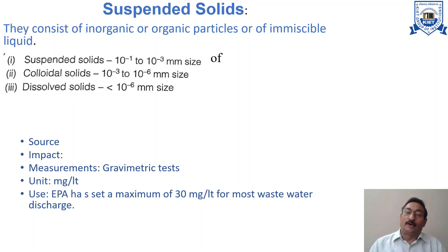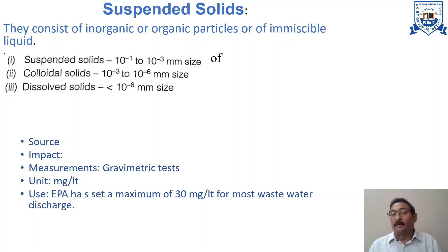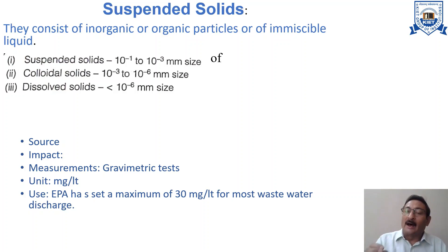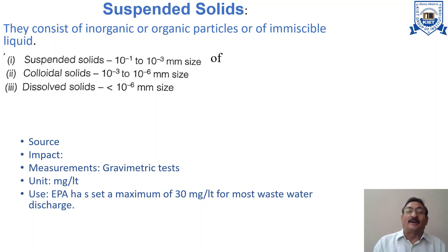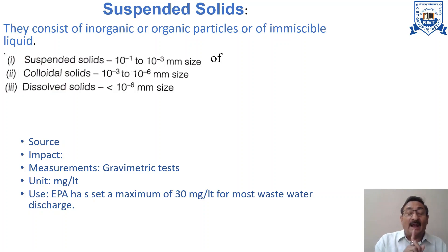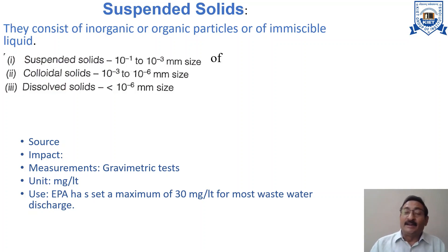The next parameter is suspended solids. Solids can be found in water in three forms: suspended, colloidal, and dissolved. When the particle size is 10⁻¹ to 10⁻³ mm, it is known as suspended solid, supported by viscous and buoyant forces in the water. Colloidal solids have a size of 10⁻³ to 10⁻⁶ mm — they are very small particles that are technically suspended but exhibit characteristics of dissolved solids most of the time. Dissolved solids have a particle size less than 10⁻⁶ mm and consist of molecules or ions held by the molecular structure of water.